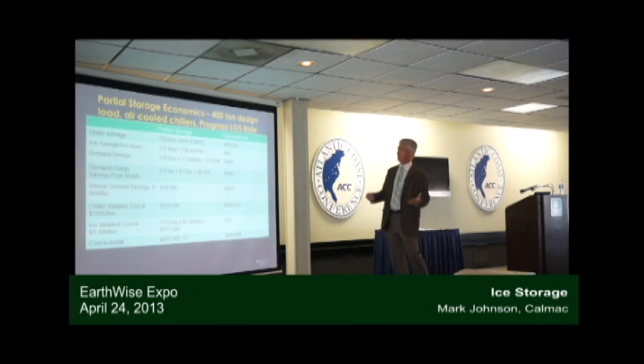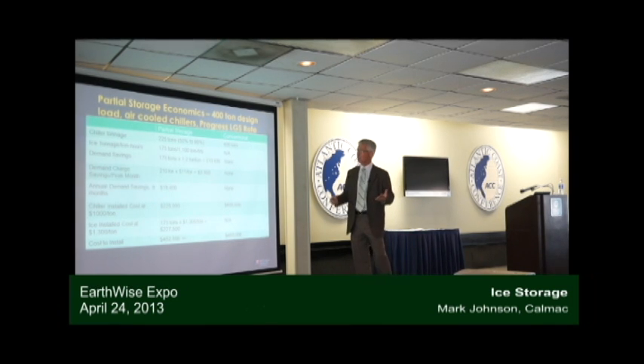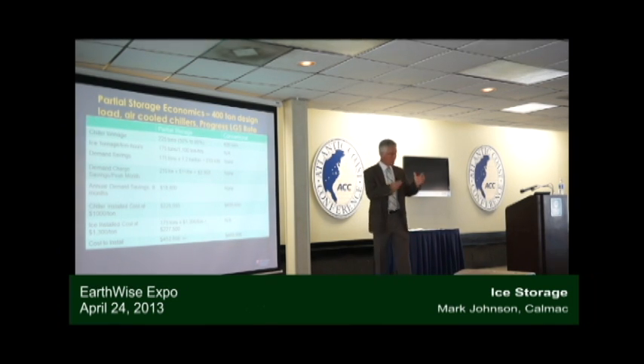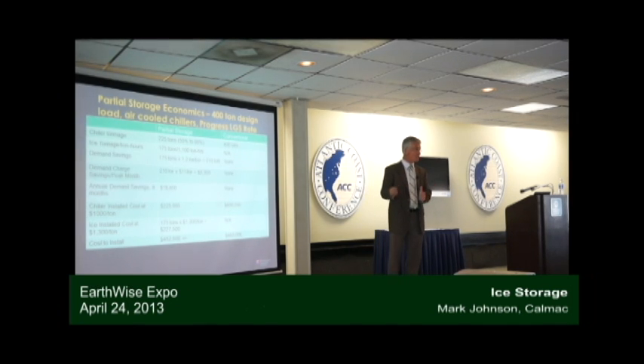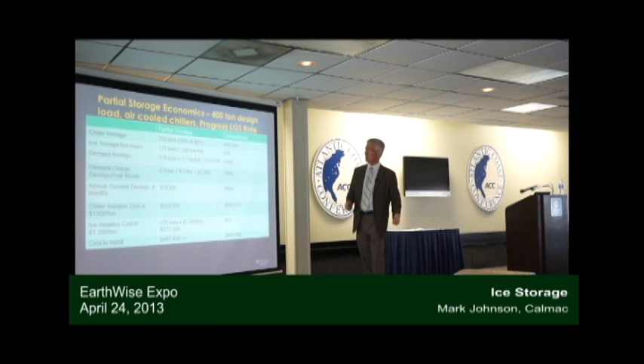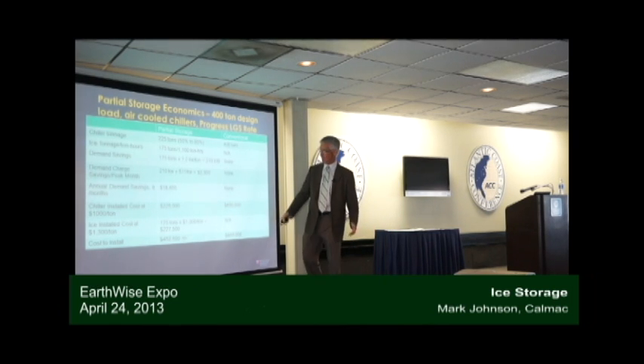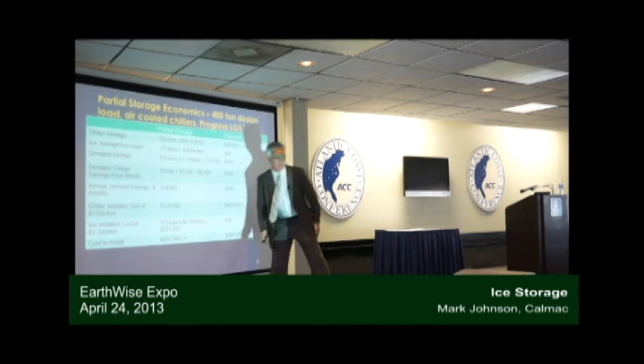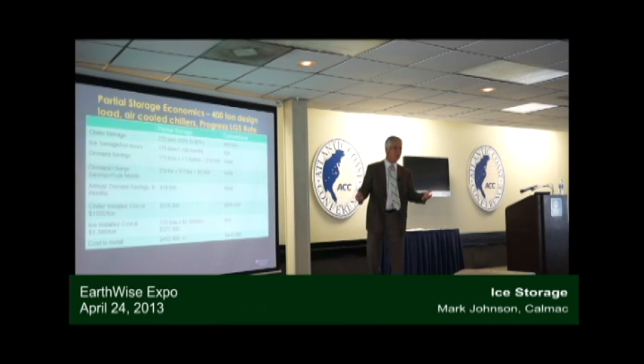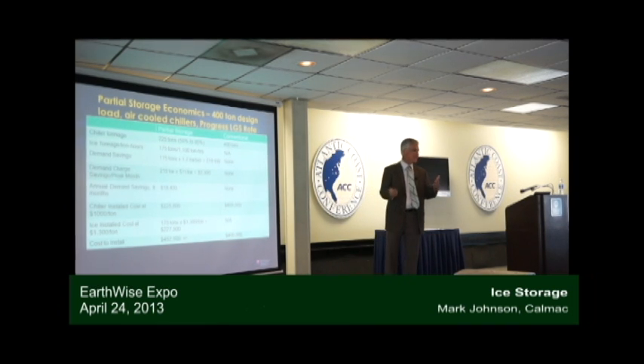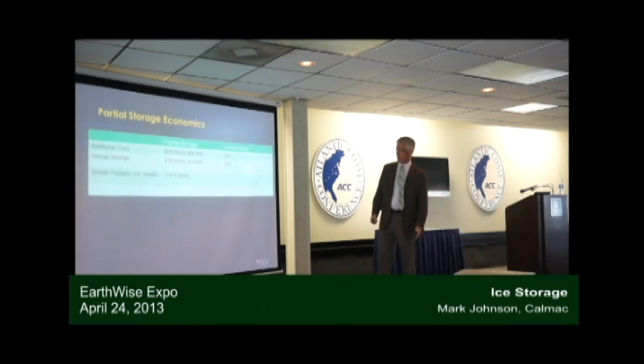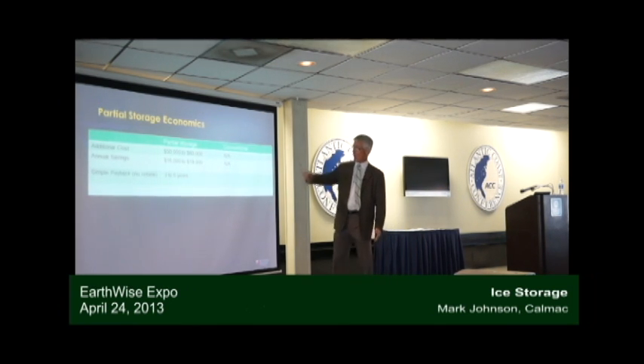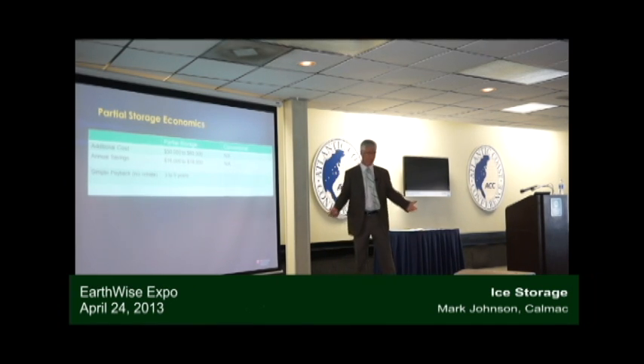There's always a payback to this. I'm not going to tell you we can do ice and chillers for the same price as chillers. We can't, but we can come close. There's an adder, and in this example the adder might be about 50 grand, might be 60, might be 70—it's in that ballpark. If you're saving $17,000 a year and having to add $50,000 to $60,000 to your first cost, that's a simple payback of 3 to 5 years.